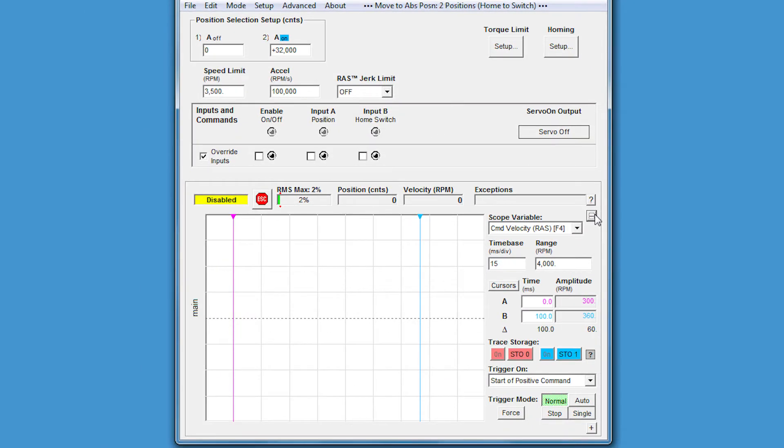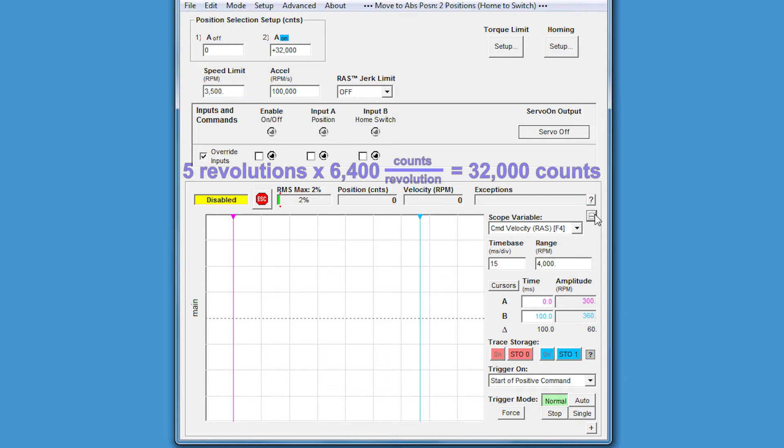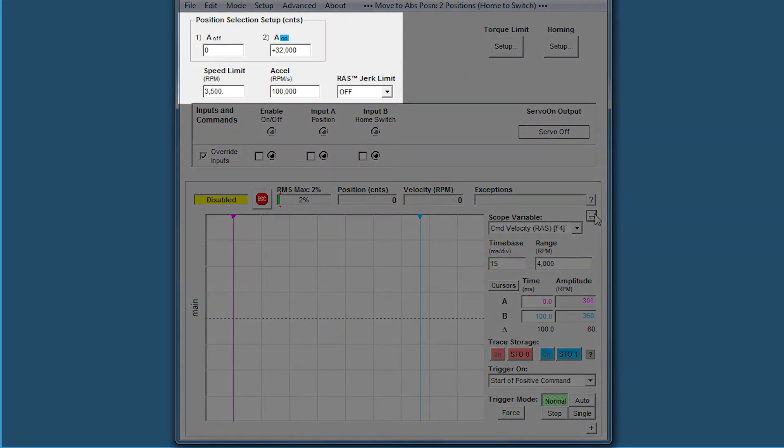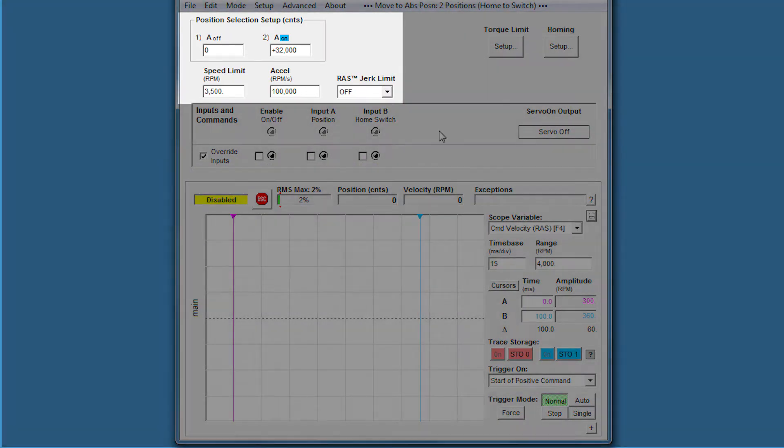In our application, we're going to run through a move that's five revolutions. Since this model of ClearPath has 6,400 counts per revolution, that corresponds to a total move distance of 32,000 counts. You can see in the top left hand corner we've set all of these parameters up beforehand.